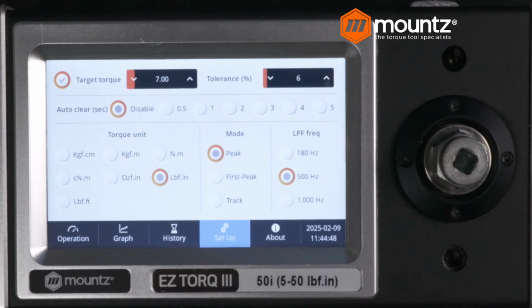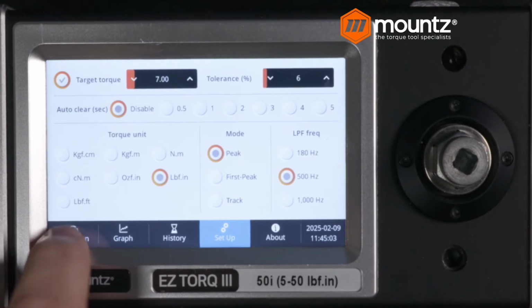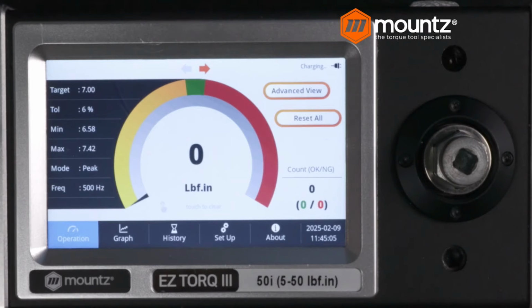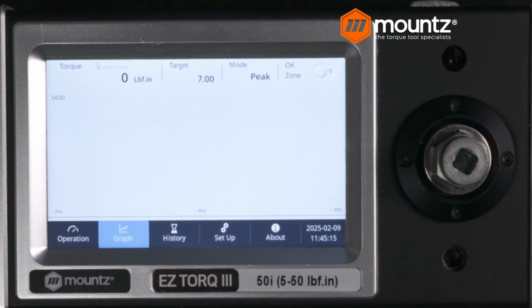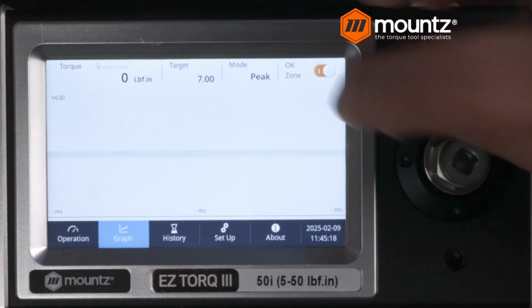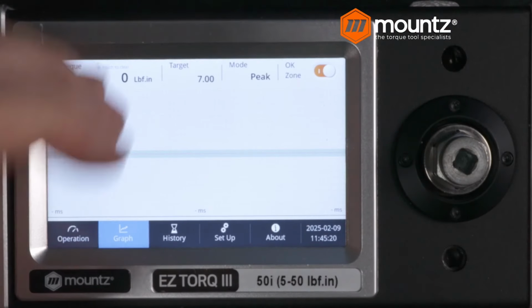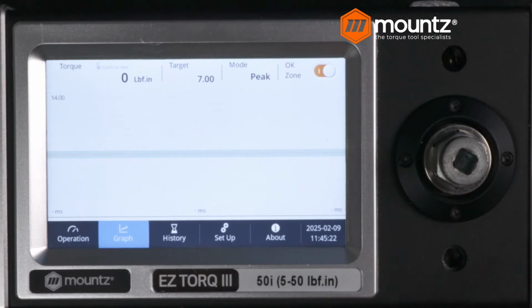And then we have our frequency here. For hand tools, 500 hertz is where you're going to want to be. Now, on our analyzer here, we do have a couple other things that we can use. If we go back to the operation mode, you can see that our min and max value have now changed. We're still in peak, and then we have our acceptable limits up here. We also have a graph function mode, and this will allow us to see what the actual value looks like as we apply load to the unit.